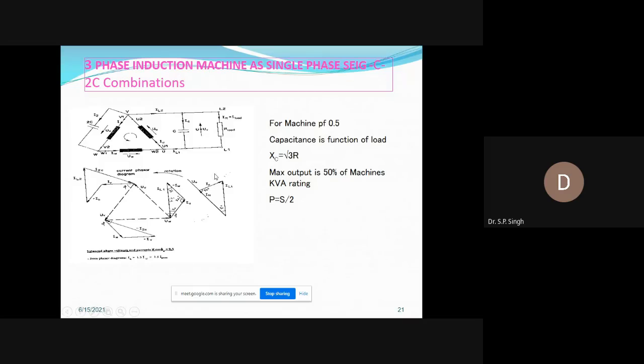balanced current in each winding can be maintained when the load resistance and the capacitance are matched, and the machine power factor is 0.5. This is the operating condition, and the capacitance is a function of the load. Depending upon the load resistance, you can calculate the capacitance with root 3 times, and the maximum output is 50% of the machine kVA rating. So P is the kVA rating divided by 2. These are the limitations of this scheme.